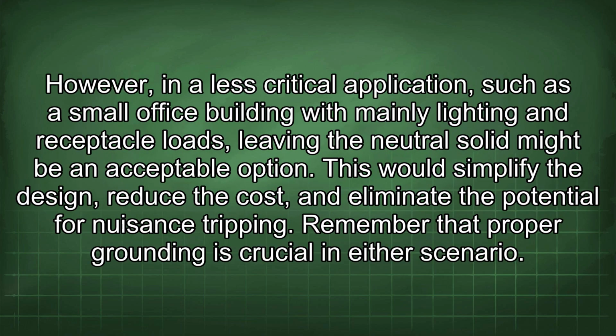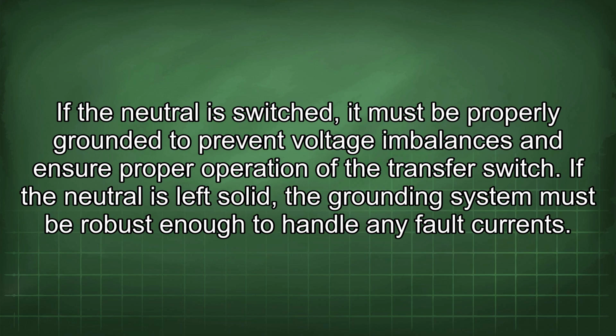However, in a less critical application, such as a small office building with mainly lighting and receptacle loads, leaving the neutral solid might be an acceptable option. This would simplify the design, reduce the costs, and eliminate the potential for nuisance tripping. Remember that proper grounding is crucial in either scenario. If the neutral is switched, it must be properly grounded to prevent voltage imbalances and ensure proper operation of the transfer switch. If the neutral is left solid, the grounding system must be robust enough to handle any fault currents.